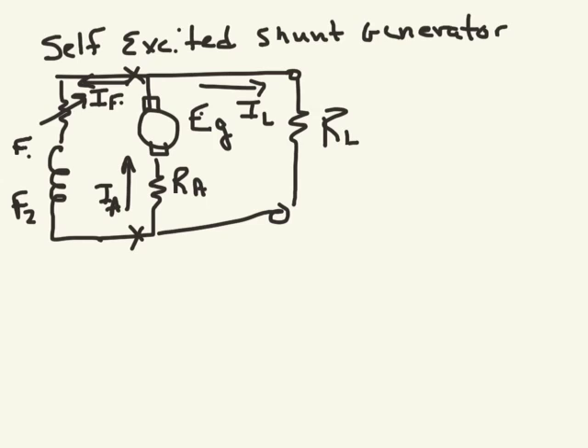In looking at how this motor will build up, initially the armature circuit, when spun with a prime mover, really isn't generating any voltage because there's no field. So we need to count on residual flux to get the motor to build, and then it will build toward its no-load voltage of EG. And we're going to use this field rheostat right here to limit the voltage and current to the specified field voltages.